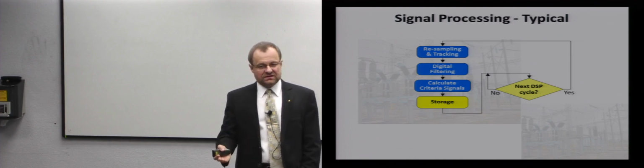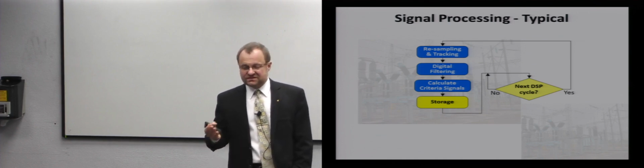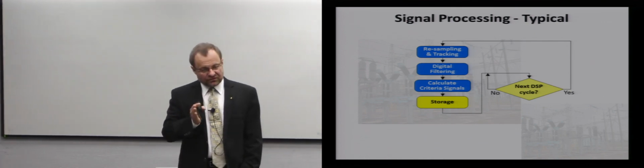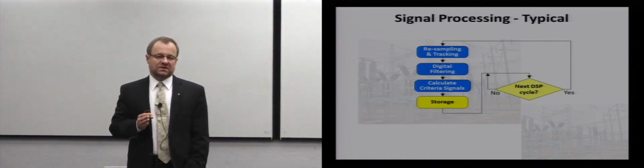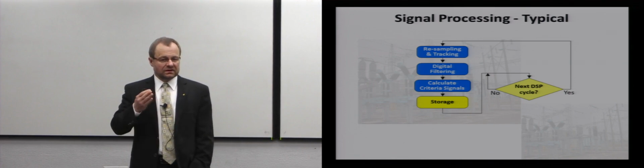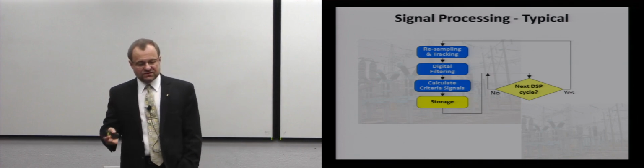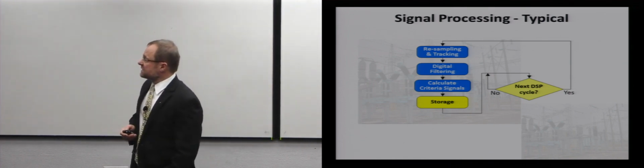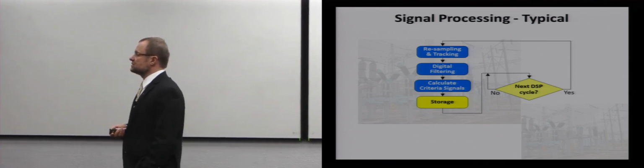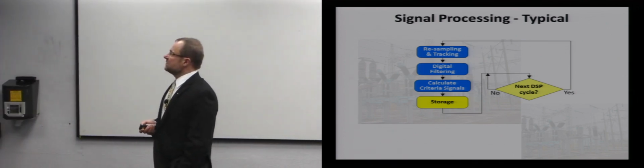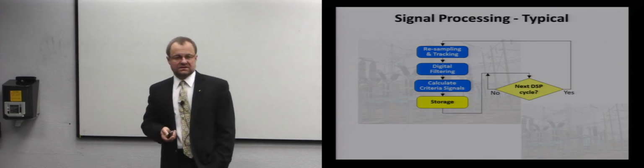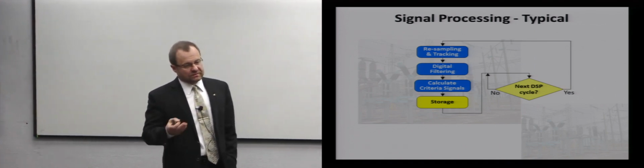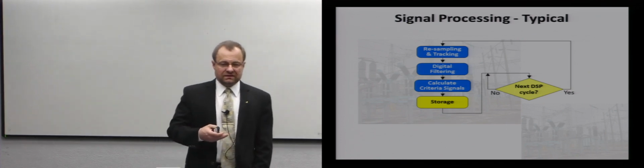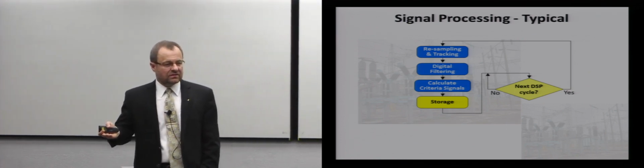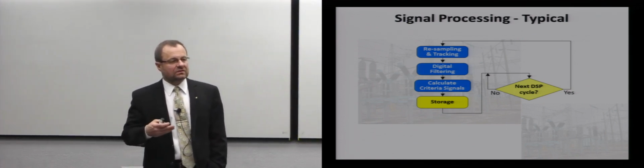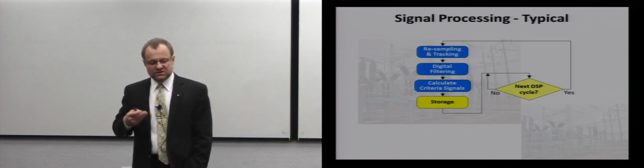Normally it's 60 hertz. It hovers around 60 hertz. It may change, right? So we have to follow that frequency to get the accurate measurement of things like power, impedance, magnitude. Then we do digital filtering to get rid of signal pollutions that could hurt us. We calculate our criteria signals, and those are things like magnitude, power, impedance, angle of the IZ minus V term, whatever it is that we have to calculate for a given function, and we store it.